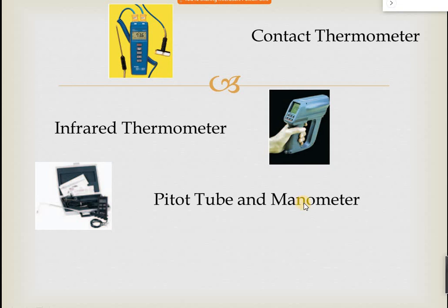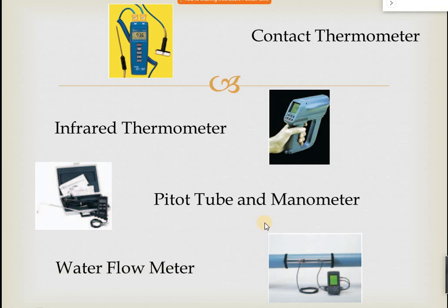Pitot tube and manometer: air velocity can be measured using the pitot tube and manometer for further calculation of the flow. This is the water flow meter, a non-contact flow measuring device using the Doppler effect, the ultrasonic principle. There is a transmitter and receiver positioned on opposite sides of the pipe. The meter directly gives the flow; water and other fluid flow can be easily measured with this meter.